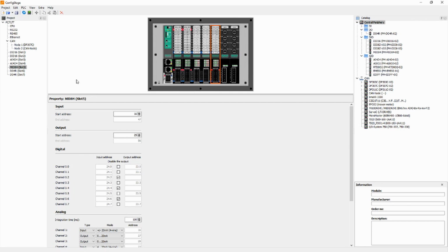And at this point, without visualization or S7 program or something else, just configuration, you are able to view the inputs inside, for example, TIA Portal or Simatic Manager. You can just connect in there to your device and open up the watch table and have a look at your inputs, so you see if everything is configured correctly and works.